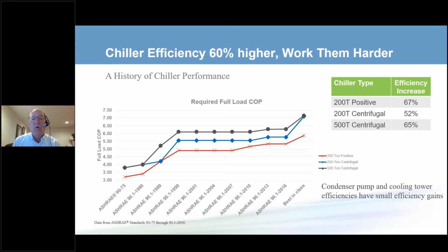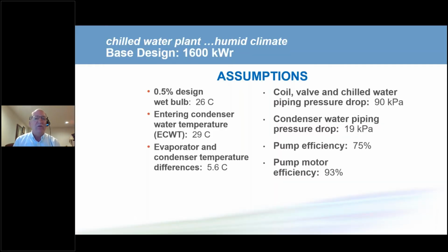We have more research done, and we have more technology done to make sure that the cooling towers are more efficient. But even though the pumps and cooling towers are more efficient, there's no way they increase their efficiency by 50 to 70%. So that tells us perhaps there's something we should look at, and we should look at why and how this affects our system designs, and why the industry is telling us to use lower flow rates and higher delta T's. So let's walk through an example.